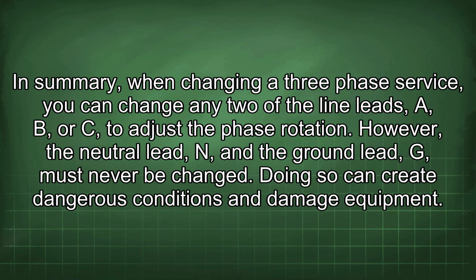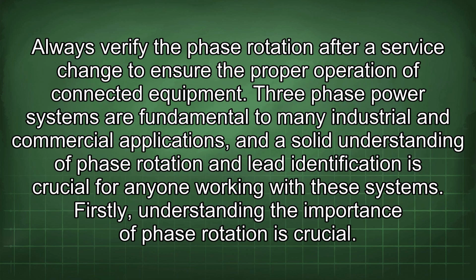In summary, when changing a three-phase service, you can change any two of the line leads, A, B, or C, to adjust the phase rotation. However, the neutral lead N and the ground lead G must never be changed. Doing so can create dangerous conditions and damage equipment. Always verify the phase rotation after a service change to ensure the proper operation of connected equipment.